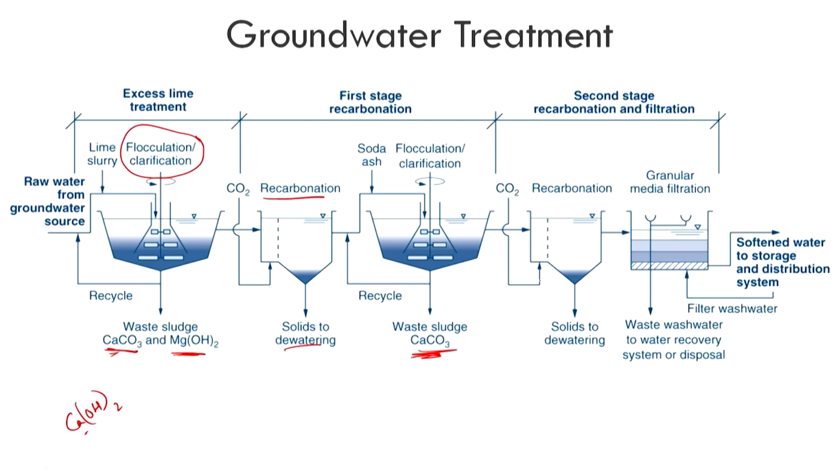Again recarbonation to decrease the pH, and then if there are suspended materials, obviously sand filtration or such, let us say, right. So, what are we doing? We are typically trying to remove calcium and magnesium, right, and then you use filtration to supply the softened water here. First, how do we do that? By adding lime, you are increasing the pH, and again same principle, or in a different application, we are going to remove the residual calcium in the form of CaCO3, right.